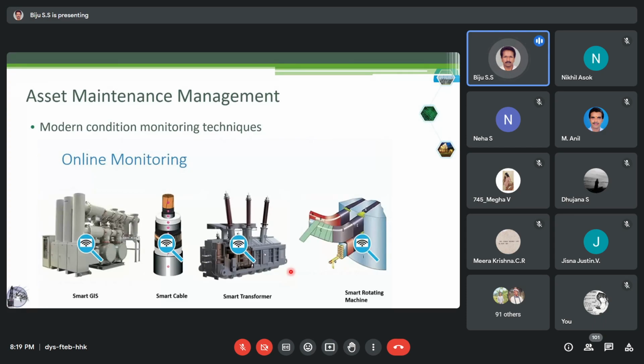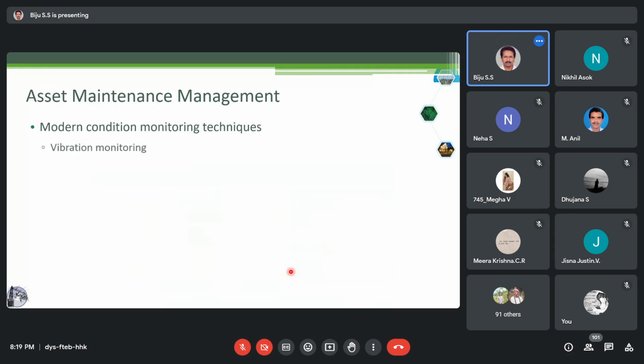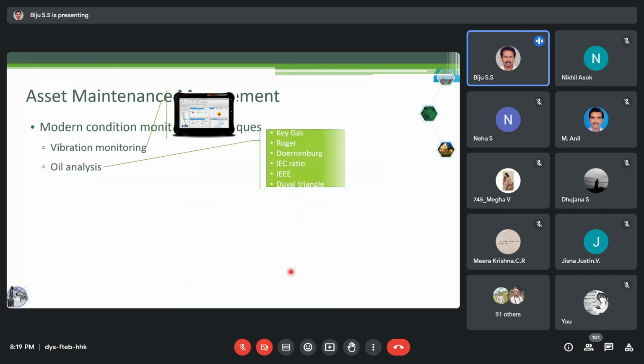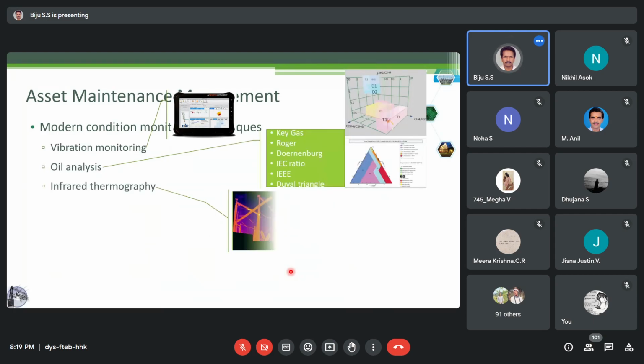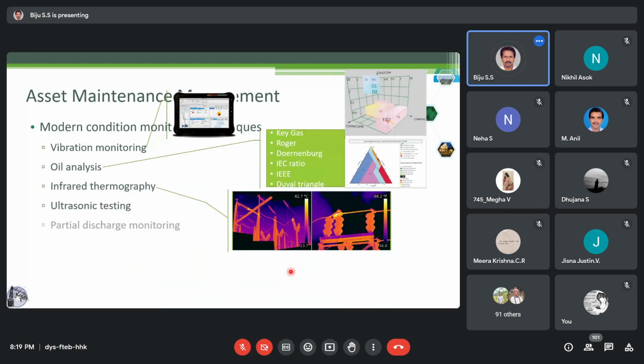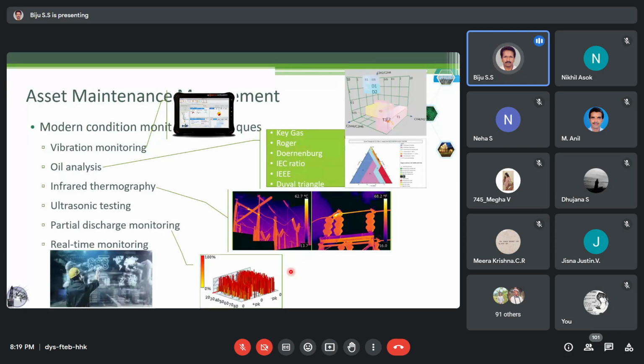So what are the online monitoring techniques? There are different techniques. I'll list some of them here. One is vibration monitoring. Then oil analysis, DGA analysis, tan delta can be done. Then infrared thermography is there. Ultrasonic testing is there. Partial discharge monitoring will be there. And finally, the real-time monitoring of all the parameters. So these are the different modern condition monitoring techniques available. I have not listed all of them, but still the most important ones are there.